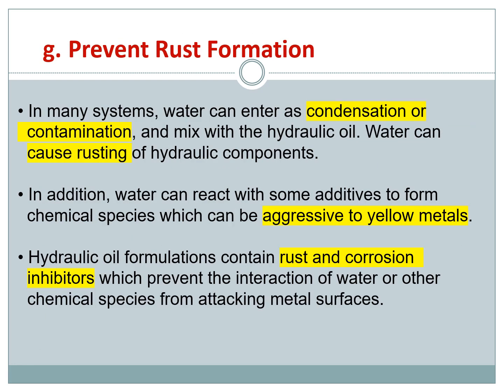The next one is preventing rust formation. In many systems, water can enter as condensation or contamination and mix with the hydraulic oil. Water droplets can cause rusting of the hydraulic components, especially those related to iron. Water can also react with some additives and chemical-based substances and can be aggressive to yellow metals such as brass. Hydraulic oil formulation must contain rust and corrosion inhibitors, and you need to have proper lubrication in order to avoid this.